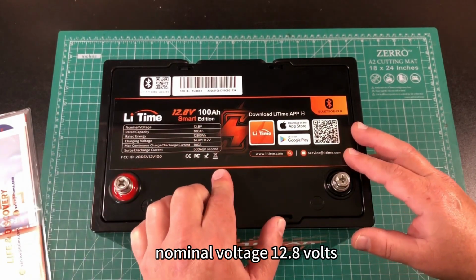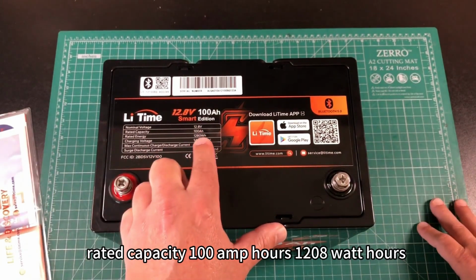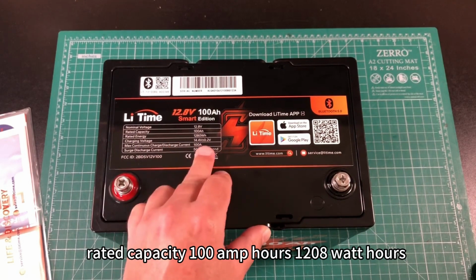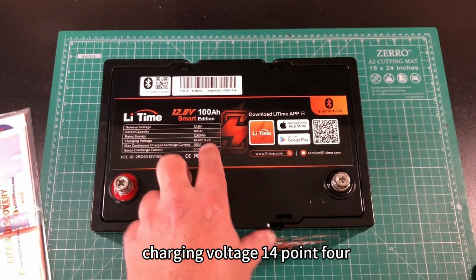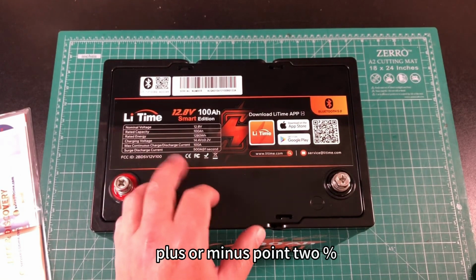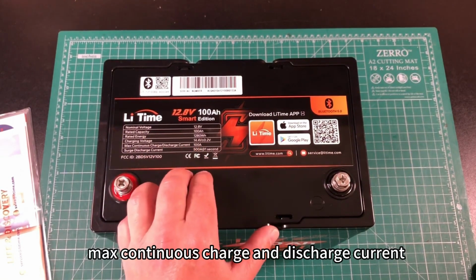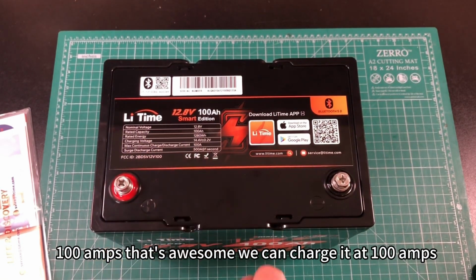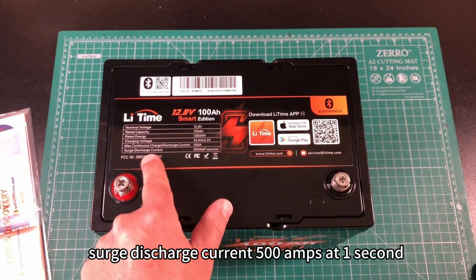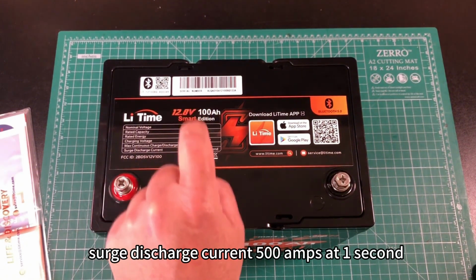Nominal voltage 12.8 volts, rated capacity 100 amp hours, 1280 watt hours, charging voltage 14.4 plus or minus 0.2 volts, max continuous charge and discharge current 100 amps. That's awesome, we can charge it at 100 amps. Surge discharge current is 500 amps at 1 second.